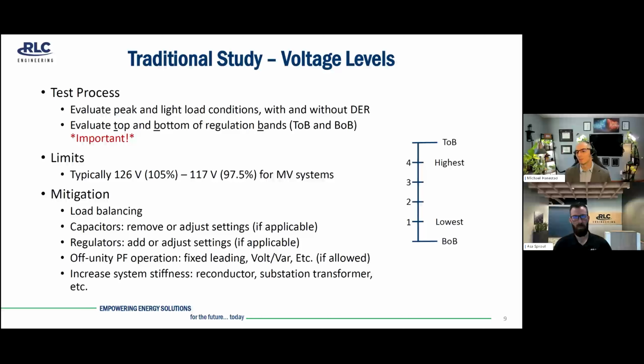But as you can see, there might still be an area of margin between that highest tap in range and the absolute maximum voltage that could be seen within that regulator bandwidth. What we found is if you're not running absolutely at that top of band, or perhaps bottom of band, depending on the scenario you're looking at, there's this window of risk where you might be missing a high voltage concern.